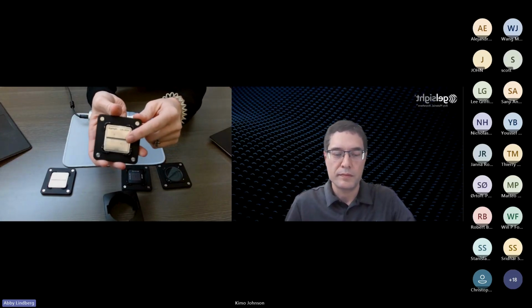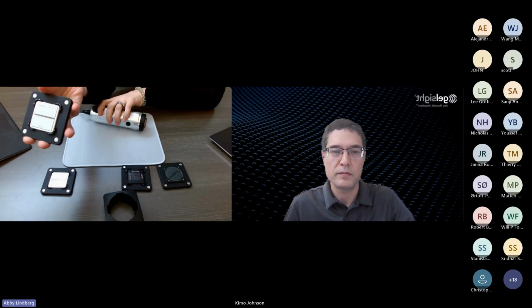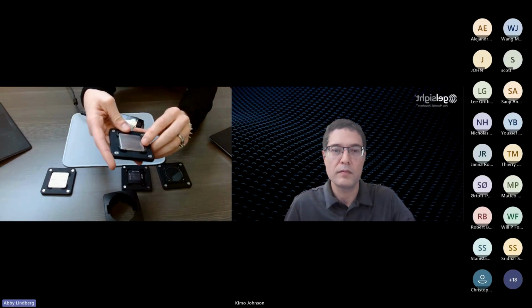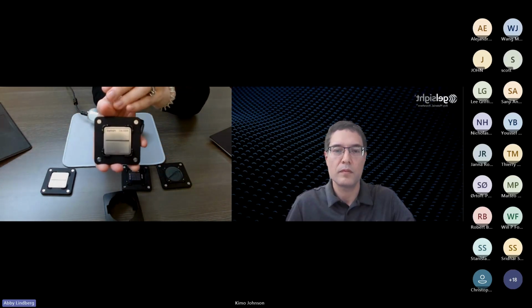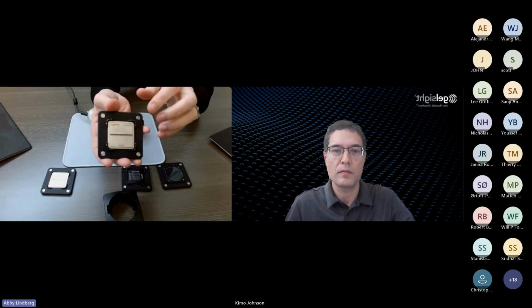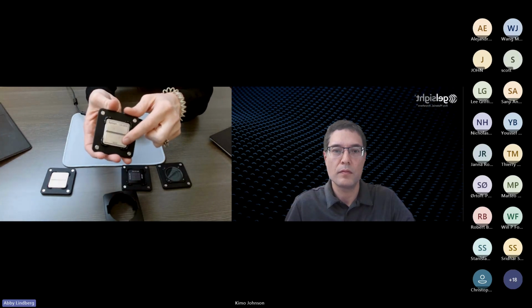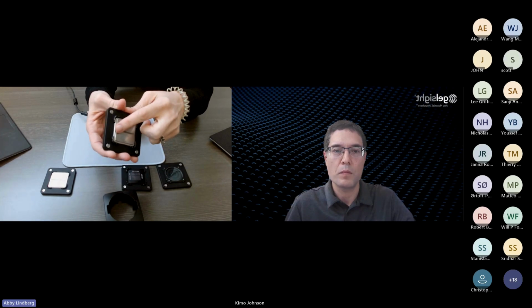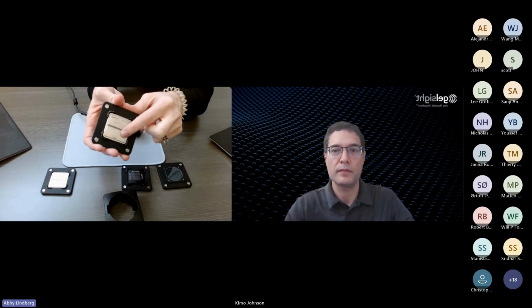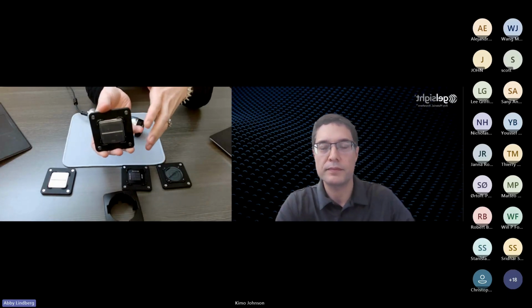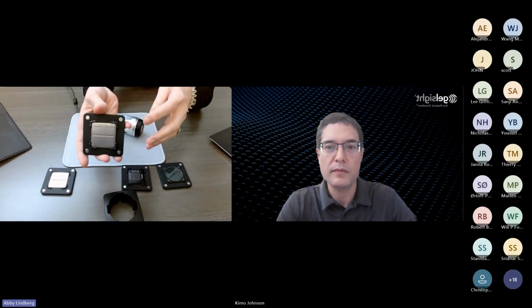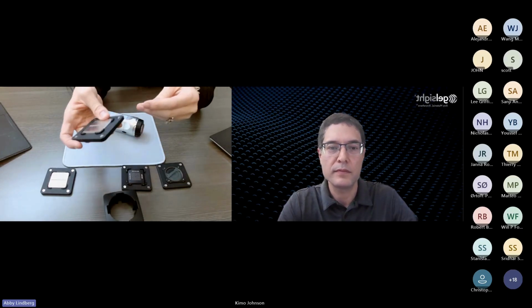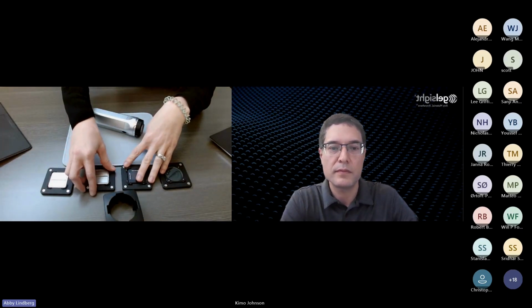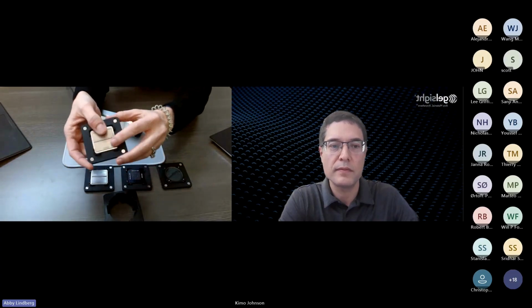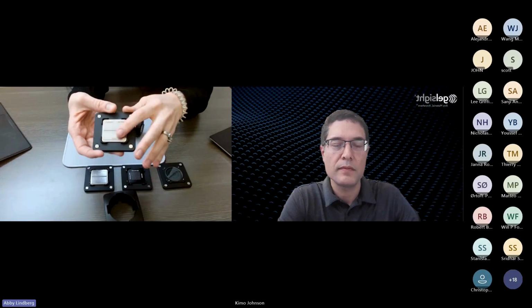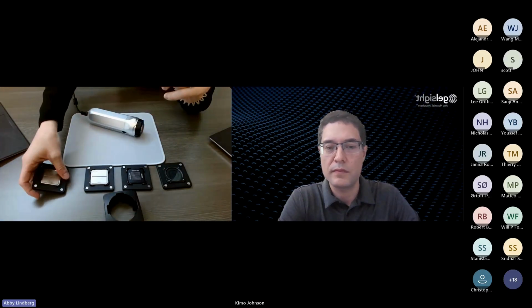We call this the G520 for our Series 2 system, which is what I have on the table here. And this is the certified target. So we have a groove here and the two holes on it with the certified depth of the groove and the certified distance between those two features to give our measurements and calibration traceability in those orientations and dimensions. And then you'll also see on the desk, I've got our validation plate, which we'll get into in a little bit. We'll start with calibration first.